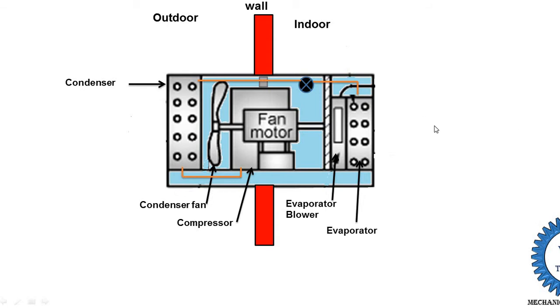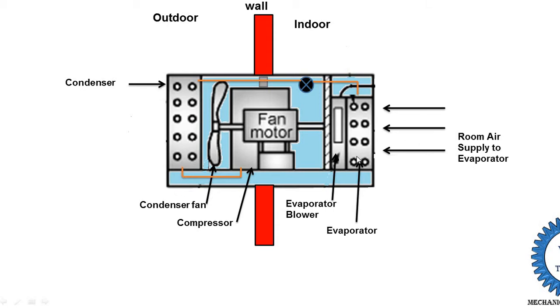Room air, which has a higher temperature, is supplied into the evaporator for cooling. This air is supplied directly to the front part of the evaporator. The blower rotates and sucks the room air — it is not naturally supplied. The evaporator contains low-temperature refrigerant, which absorbs heat from the air, reducing the air temperature. This cooled air then comes out from the front of the evaporator and is supplied to the room.